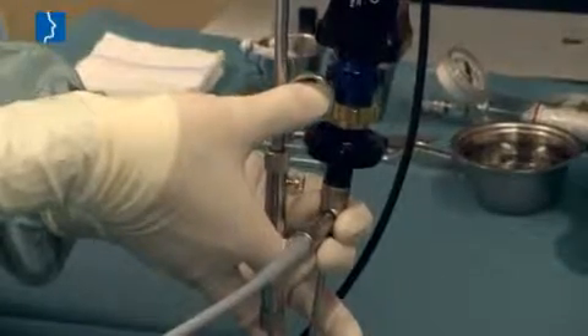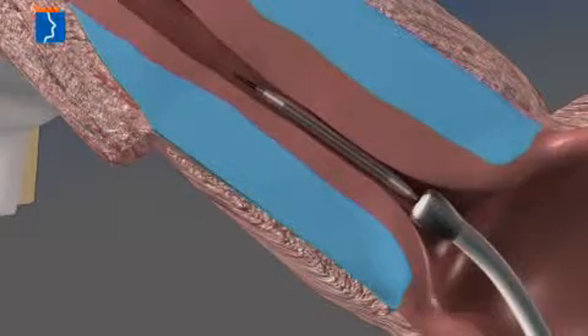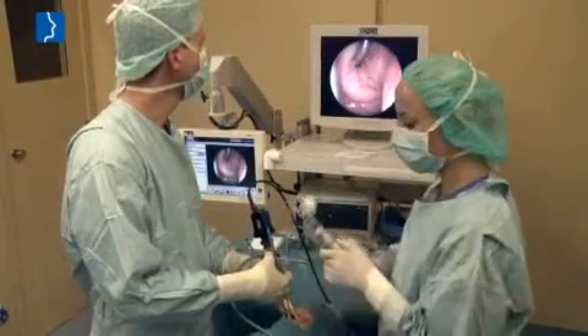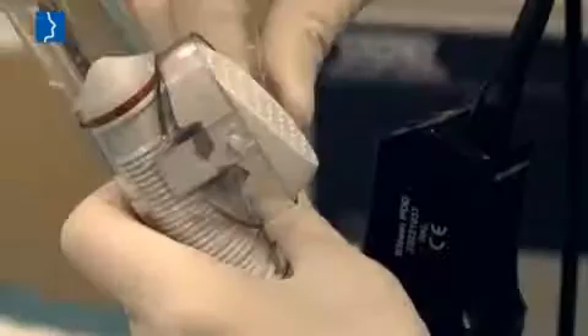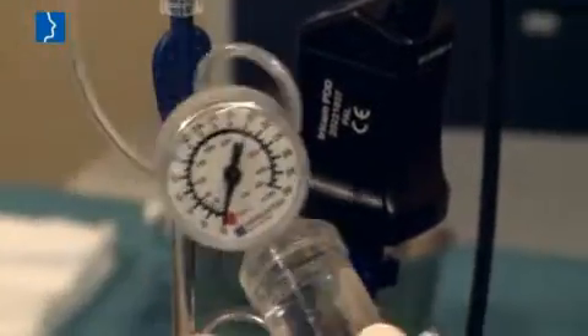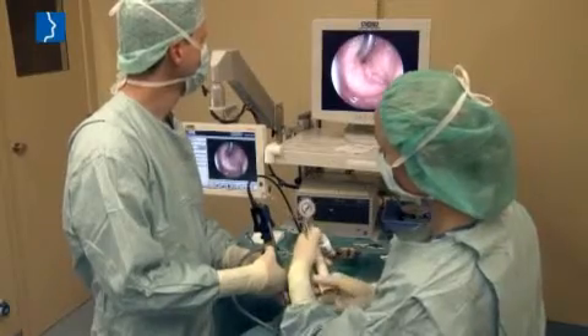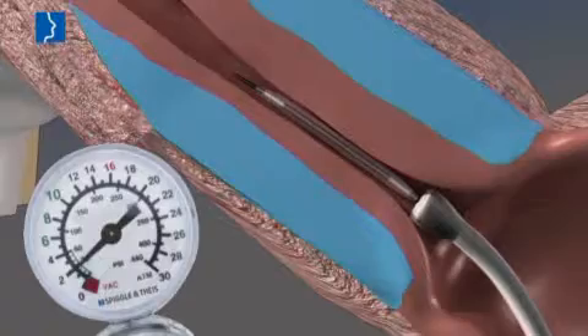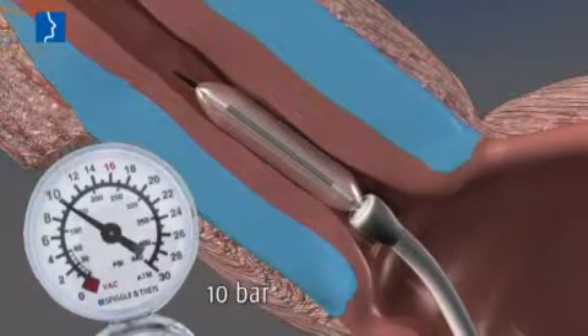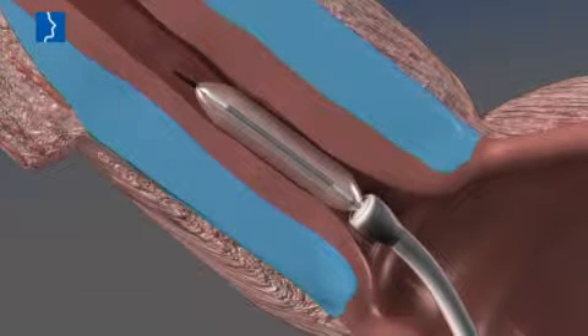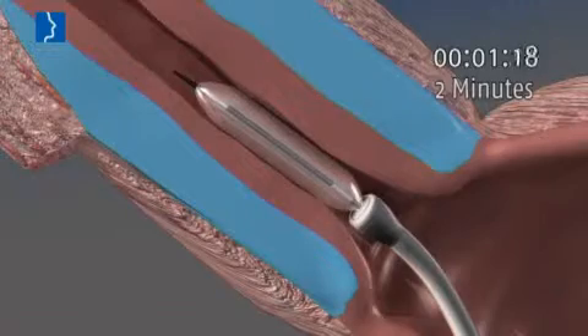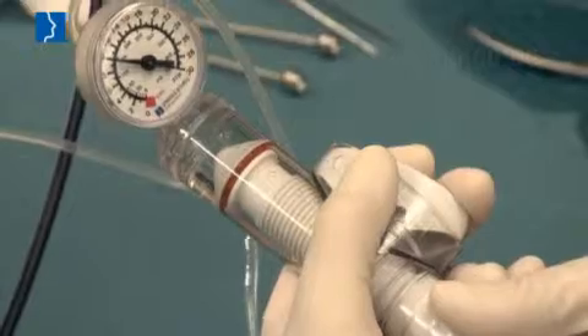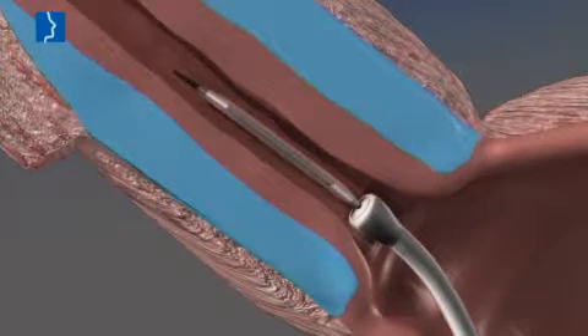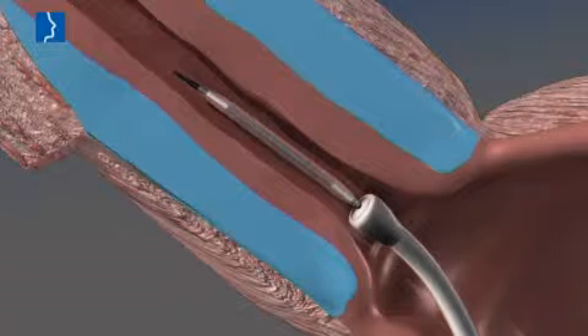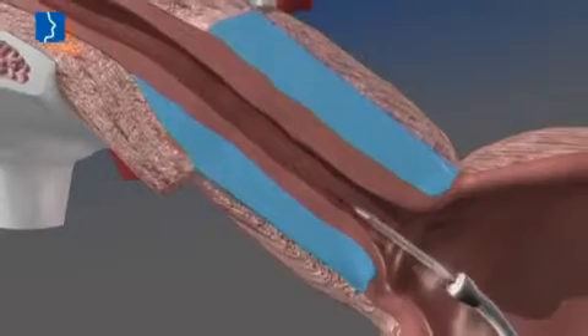Now push the balloon catheter forward smoothly. Connect the inflation pump with or without extension with the catheter. By performing a screwing movement at the inflation pump, now fill the catheter up to a pressure of 10 bar. This way, the balloon catheter will dilate the narrowed area of the eustachian tube. Hold the pressure steady for 2 minutes. Release the quick lock, relieve the pressure of the pump, and aspire. The eustachian tube has been dilated. Remove the insertion instrument with the catheter from the eustachian tube.